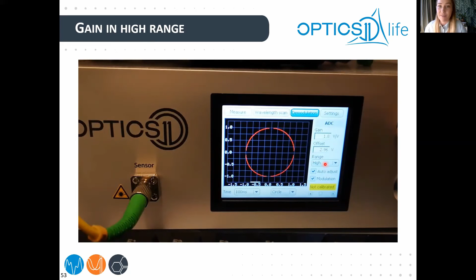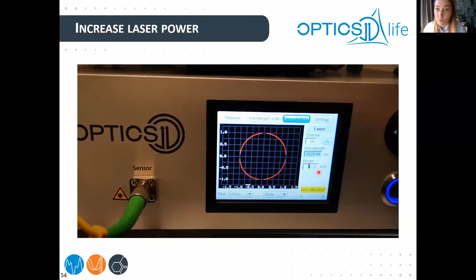Now, the first thing we check is really if the signal is in high range. If it is in high range, what it means is that the gain is high. High gain is high noise. We can decrease that by moving to another window and finding the power. So this is laser power. Probably the default laser power that you have is 6.31 milliwatts.